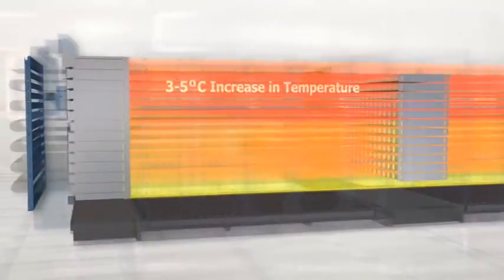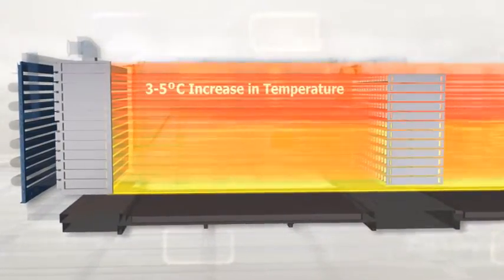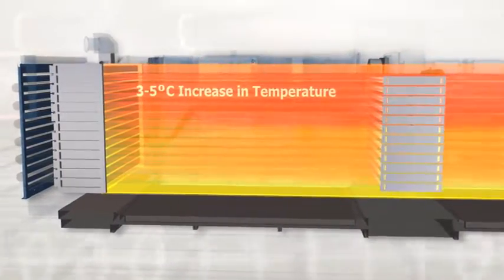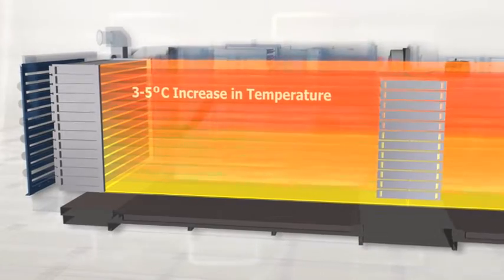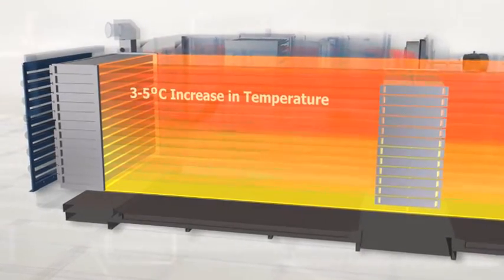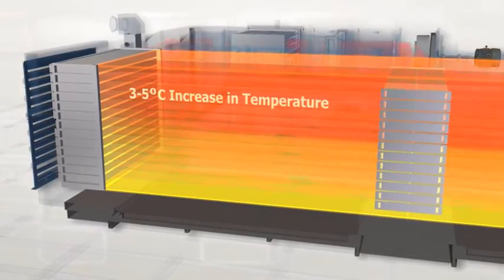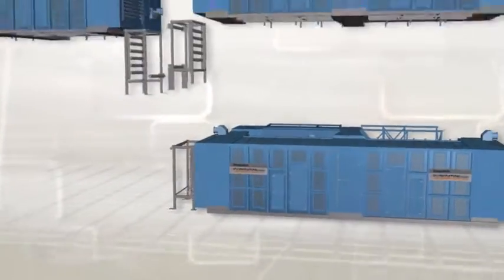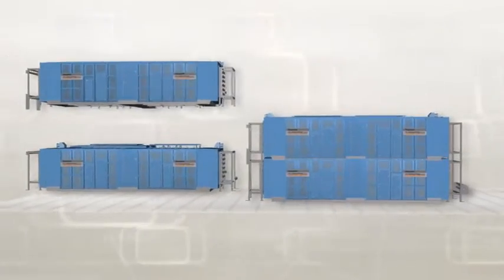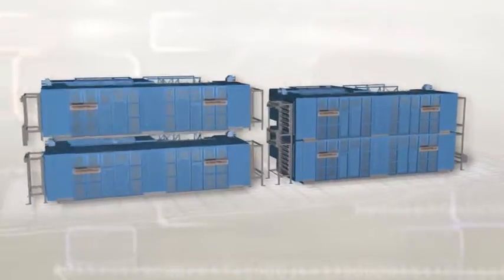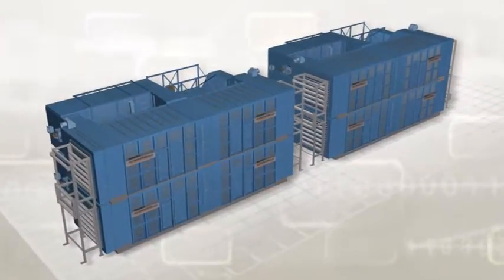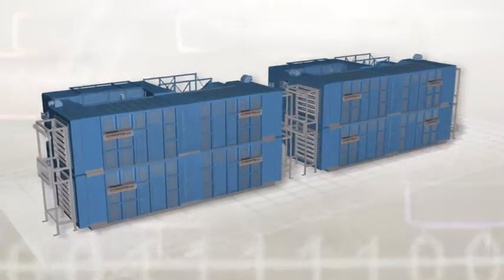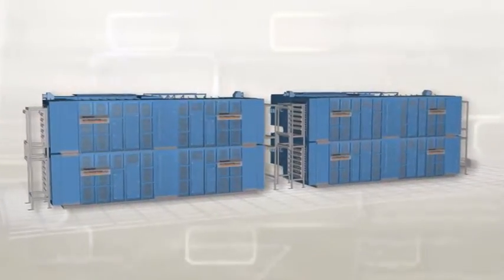Split-zone control provides two discrete thermal profiles for the upper and lower half of the chamber. Separate plug fans and controls allow you to increase the temperature in the upper half of the oven by several degrees, advancing the rate of oxidation of the fiber. Because each oven is now split into two zones, the number of ovens required to properly oxidize the fiber can potentially be reduced. This results in a needle-moving reduction in capex and operating costs.